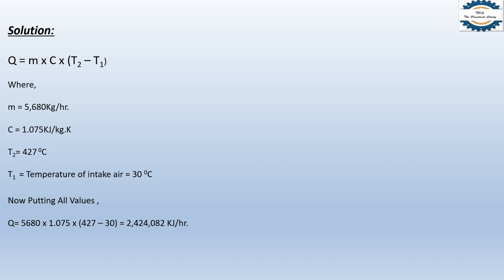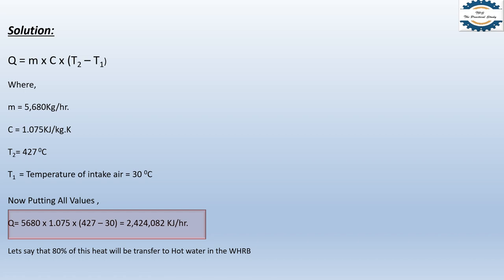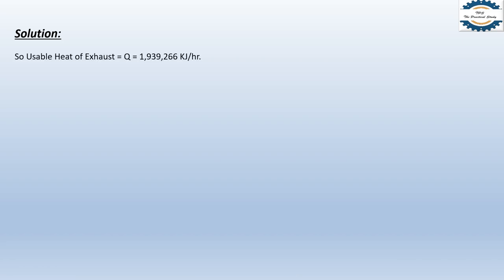Putting all the values in, we get Q = 2,424,082 kilojoule per hour. This is the total heat available in the exhaust of the gas generator. However, not all of this heat is converted into steam — it depends on boiler efficiency. Assuming waste heat recovery boiler efficiency of 80%, the usable heat available for steam production is 1,939,266 kilojoule per hour.